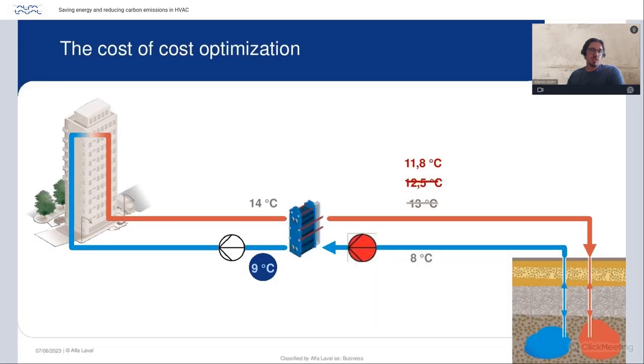More water on the cold loop means that the temperature going back to the wells is also shifted. So instead of 14 to 9 and 8 to 13, you will now have 14 to 9 on the building side, but on the well side, you will have 8 to 11.8. So there's a quite big temperature deviation going back to the wells.